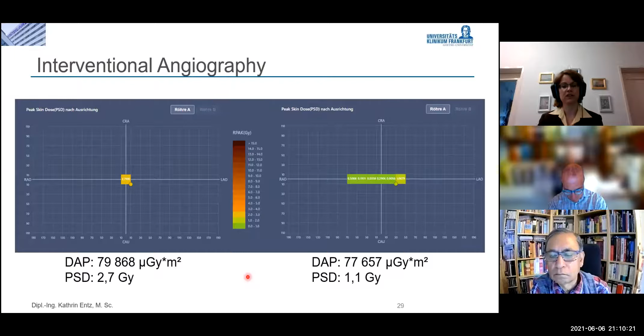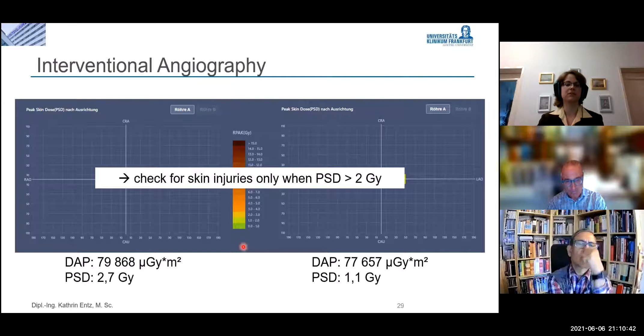And it means that not because you're exceeding the 50,000 microgray times square meters, which is the reporting level for us, that we're actually damaging the skin of the patient. So we only check for skin injuries and call a patient back when we can see here from those graphs that the peak skin dose is actually exceeding 2 gray. It is still not the limiting value for deterministic effects of grade 2 or higher, which is 5 gray, but we use that as a little bit of error margin. So if the calculation in this case is not absolutely correct, we can still find skin injuries if they happen to be above 2 gray.